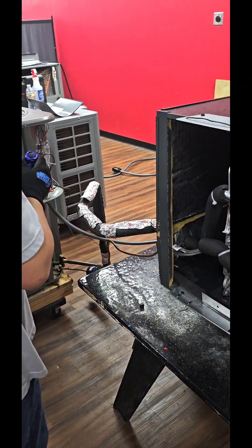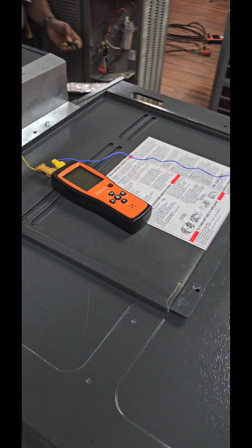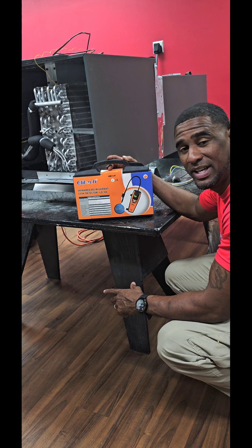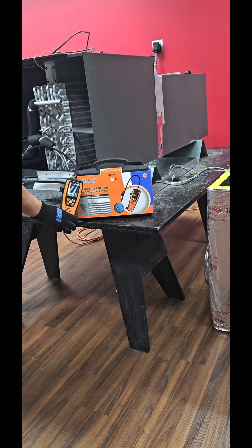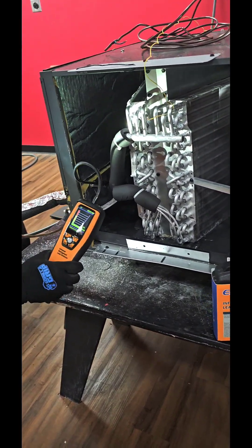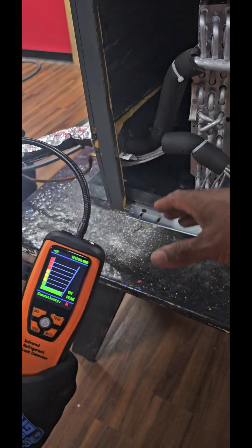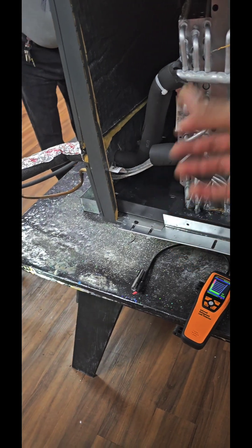With this you can put it on the valve itself and change your valve without losing the refrigerant. This is the infrared leak detector — visit elitechus.com, that's the ILD300. You got maximum proof now, you can use it right there on the spot. It's his first week in class and he already found the leak. We got it now — it was a little straight up. This thing don't lie. That's how you can learn real quick. He found it, it went off. It was leaking, it told you it leaked. You tightened it up with the correct tool and we checked it again.